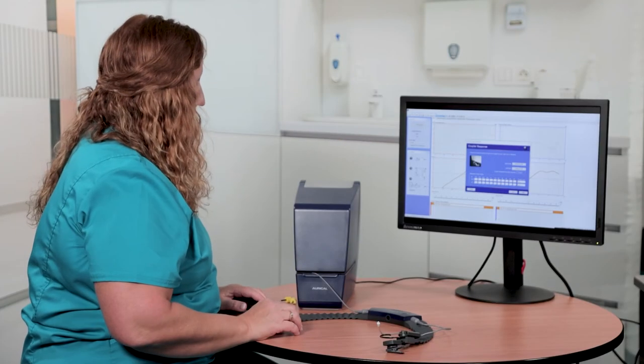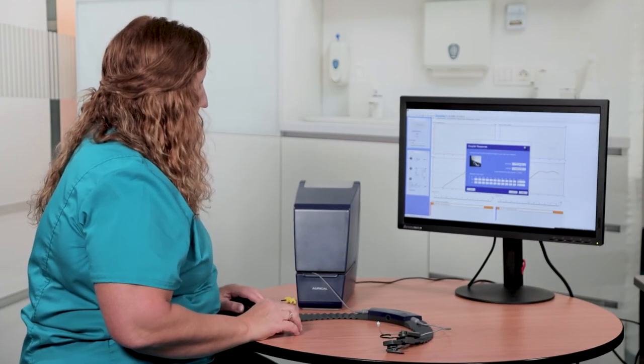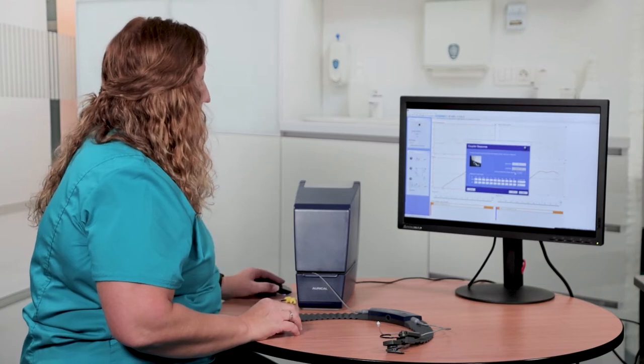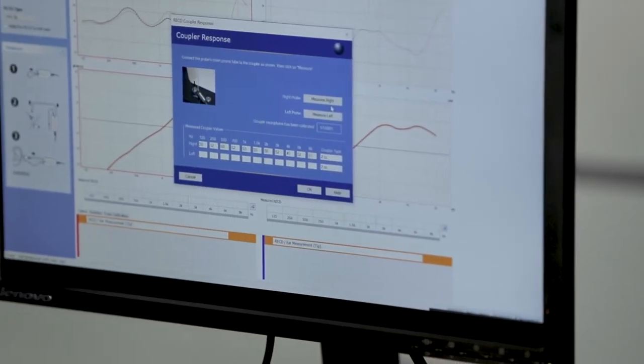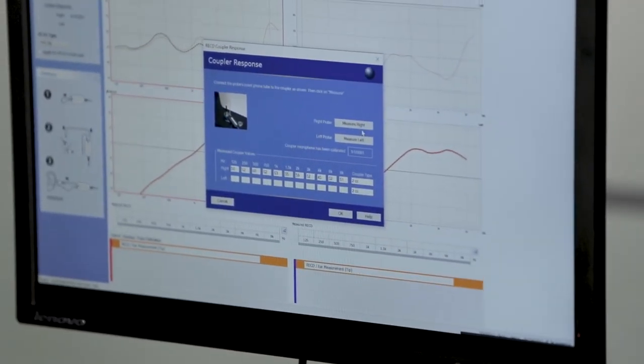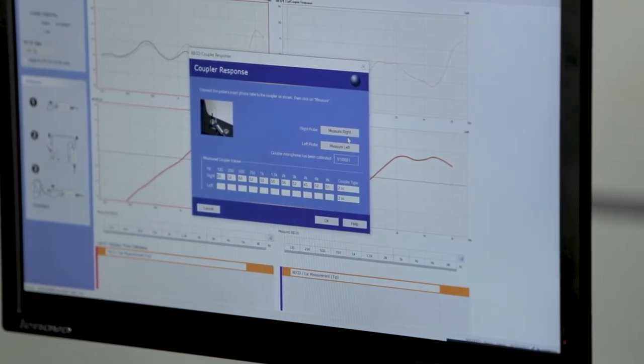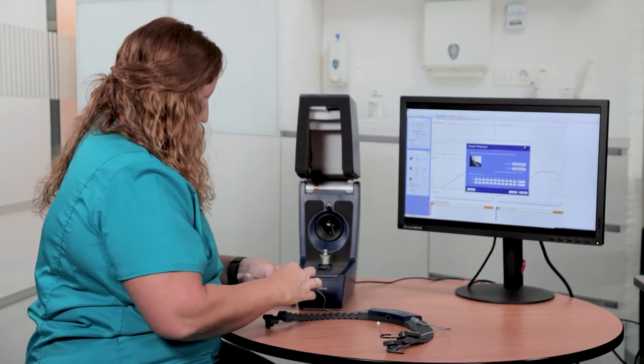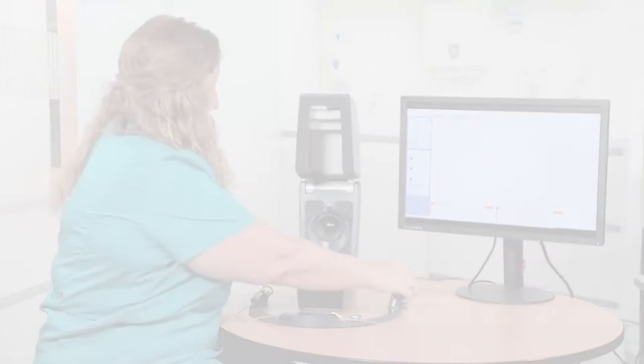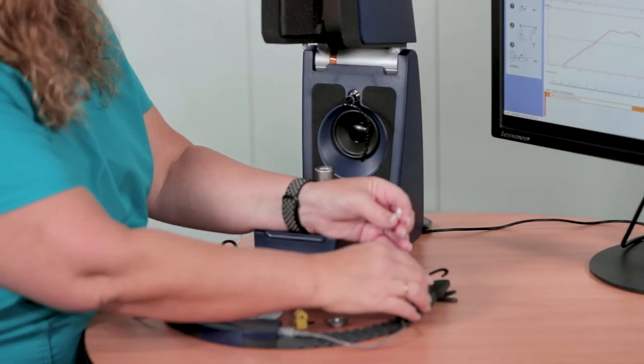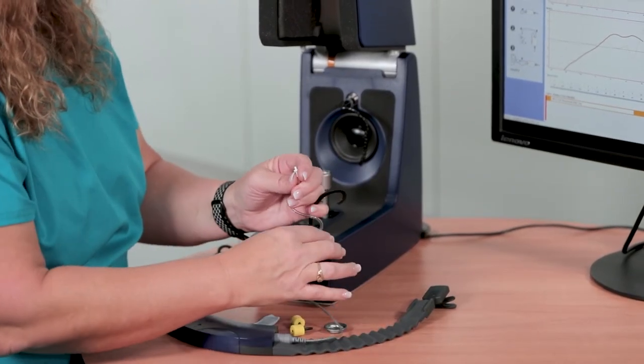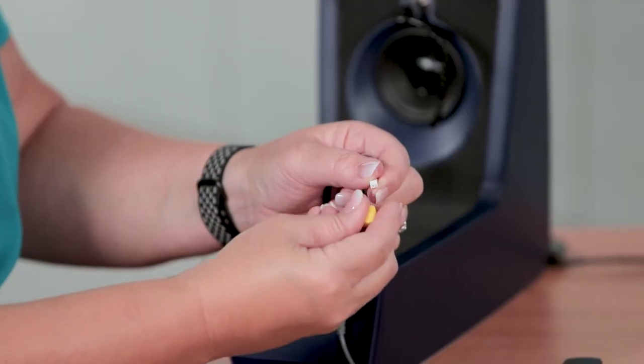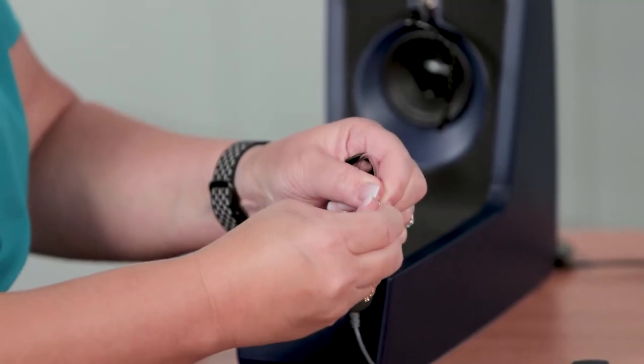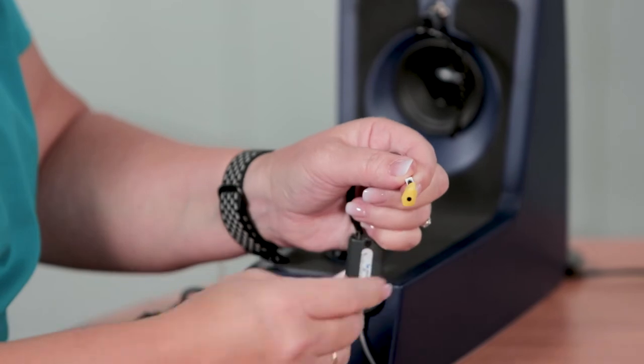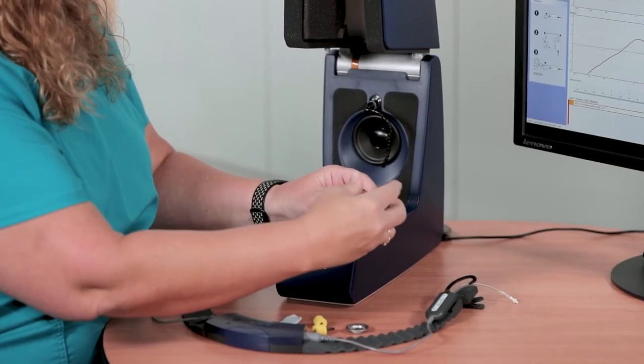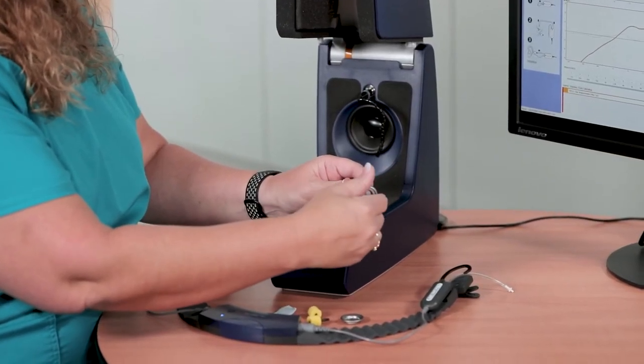When coupler response is selected, the on-screen picture will provide an example of the appropriate coupling for the Aurical FreeFit probe and HIT coupler. The first demonstration shows the proper setup when preparing to measure the coupler response with the HA1 coupler with tip. Attach the RECD transducer tube to the Aurical FreeFit probe and attach the foam tip to the tube. Twist the 2cc adapter onto the coupler microphone.